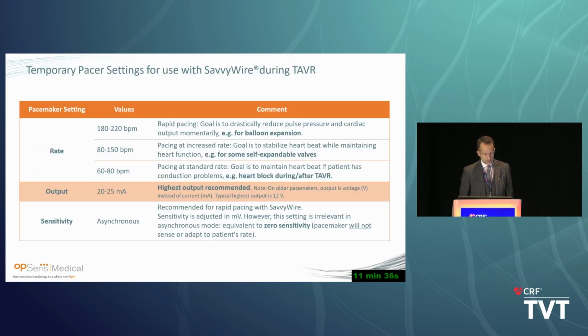You can see at the bottom there. You can really pace at any rate here, 60 to 80, just to pace a controlled rate. Let's say if you have heart block afterwards, it's safe to use it for that, and then if you're going to put in a more durable solution and send them to either the ICU or the floor afterwards, it's safe to pace at that rate.